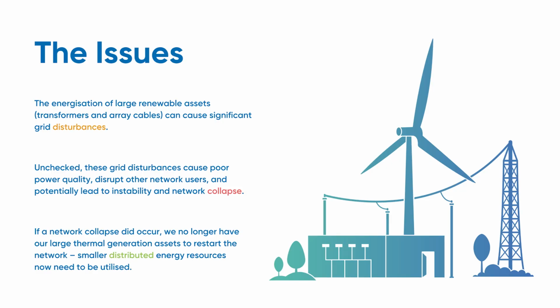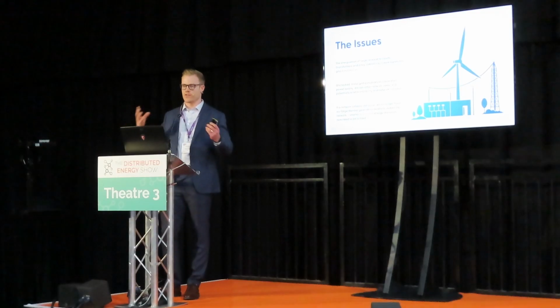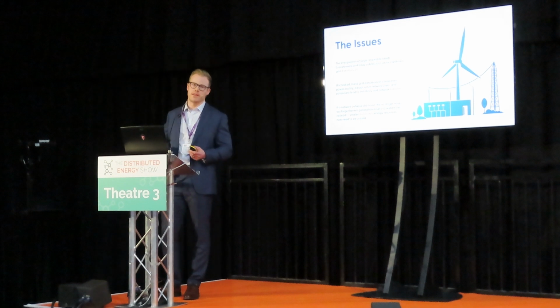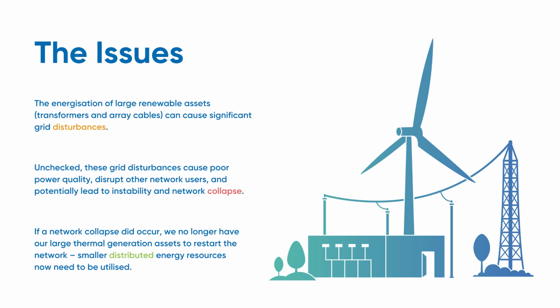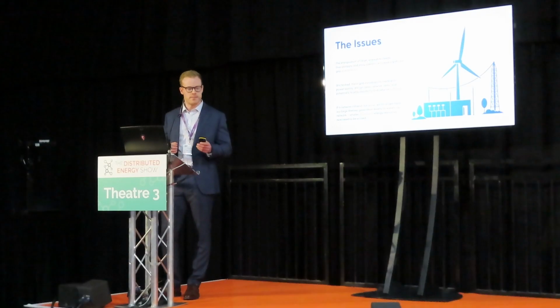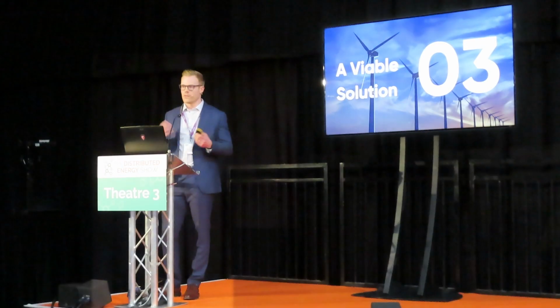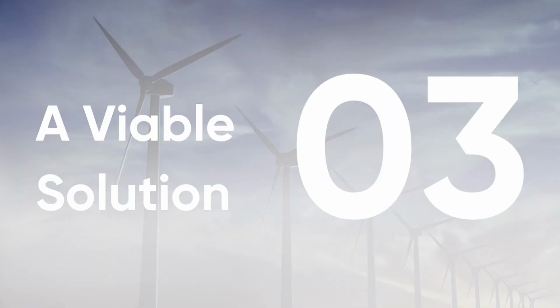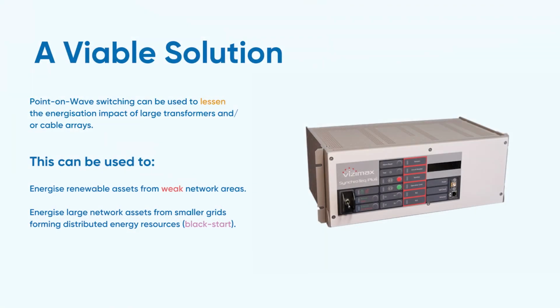So you've got this weak network with a weak asset, with massive wind farm assets and transformers and cables. You're trying to energize them. They're creating transients, inrush currents, and the stability and grid strength is just not there to support these large assets. So what's the solution? One viable solution is the use of point-on-wave switching.